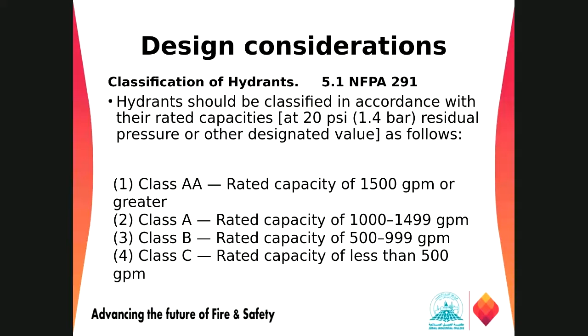These are some markings. Class AA means the capacity is 1500 GPM or higher. Class A means between 1000 GPM to 1500 GPM. Class B means 500 to 999 GPM, and class C means less than 500 GPM. So these are the requirements of NFPA 291, and based on that we have to do the marking for the hydrants, the color code and all requirements.